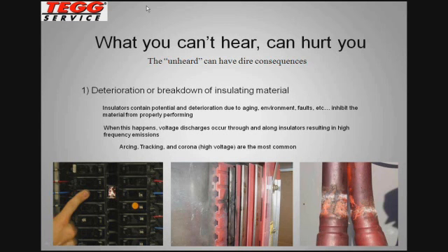And in the images you see on the screen right now, that would be visualized examples of each of those anomalies. On the left is a 20-amp circuit breaker that was arcing on the line side connection. Fortunately, it did not go to another phase. The middle image shows an I-Line Square D panel where there was a bunch of tracking occurring on some of the circuit breakers, and the telltale sign there was the carbon trails that were left on the bus and the Bakelite material, the insulating material there. Finally, on the right, you have some high-voltage terminations where corona had been taking place for whatever reason and became destructive in nature, with the watermarks and trees and spidering trails, which are a telltale sign of that.